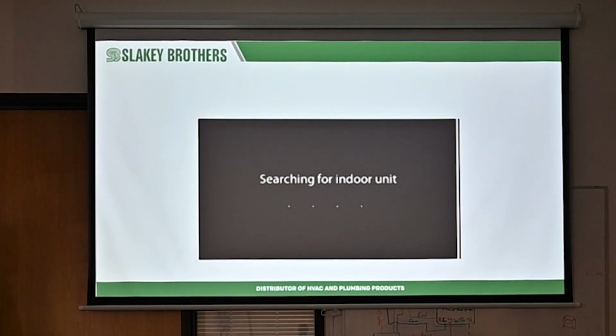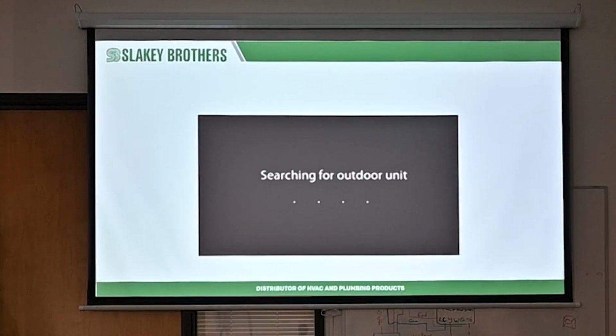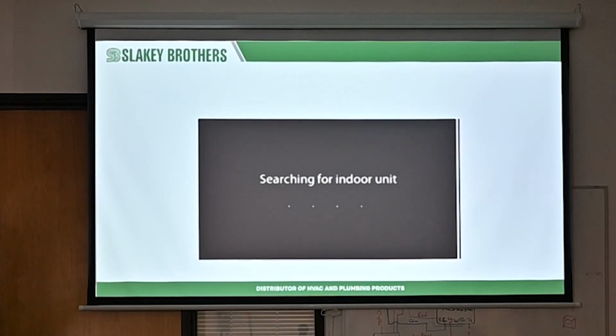And again, we're going to be breezing through some of this stuff because it's pretty generic. It's just going to start reading this. Searching for indoor unit. It found the unit. At any point, if it doesn't find the indoor unit or it doesn't find the outdoor unit, it's going to stop. It has to find the indoor unit minimum for it to even go on to the next step. Okay? If it doesn't find the indoor unit, crap. Let me see what my problem is.